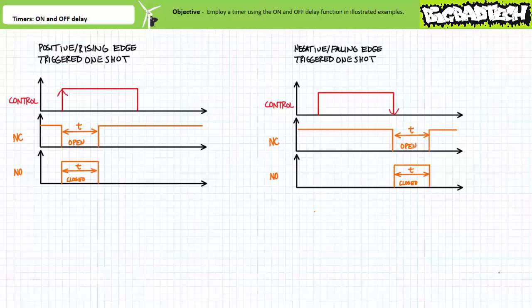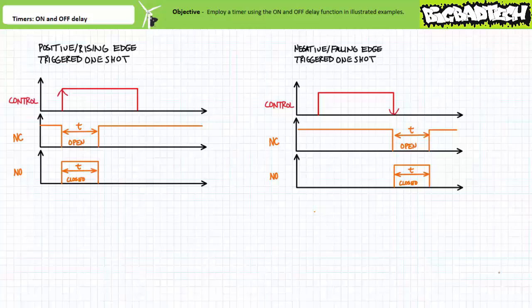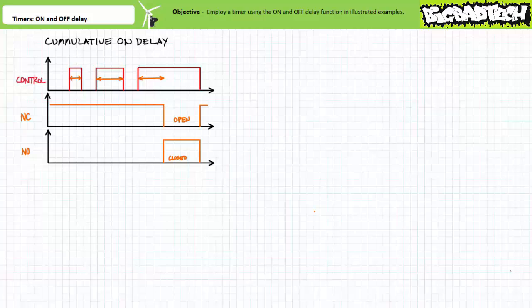Finally, compare this behavior to a timer executing the cumulative on delay function. A cumulative on delay timer is a record-keeping function where the timer keeps track of how long its controlling input has been energized. Only after the controlling input has been asserted for the predetermined period of time do the outputs respond — despite the controlling input being discontinuously energized. Such a timer could be used to track how long a controlling input has been asserted and alert the system that maintenance must occur. I like to think of cumulative on delay timers as little accountants that keep track of how long the controlling input has been asserted.